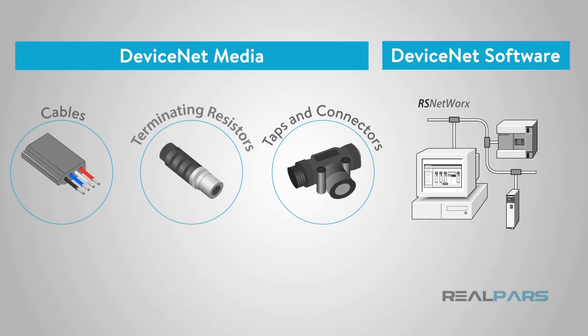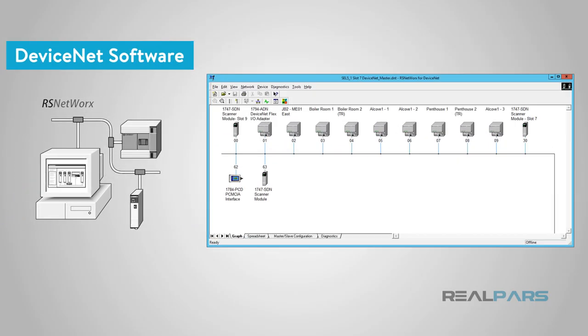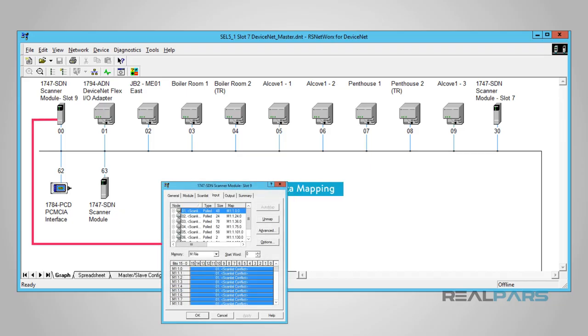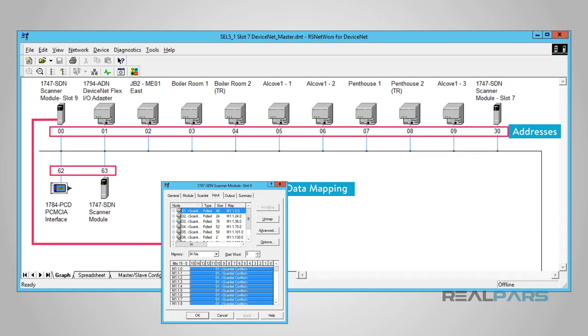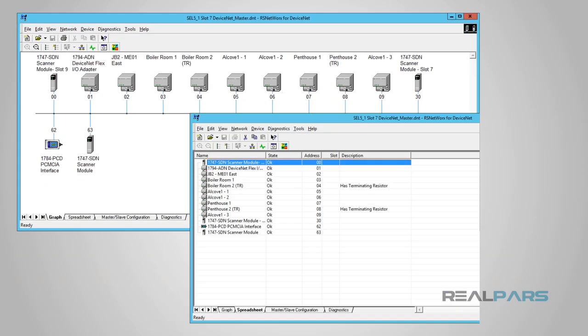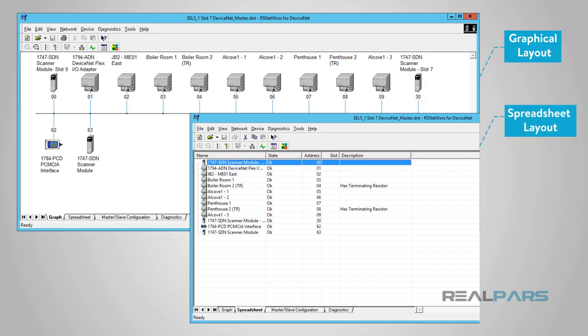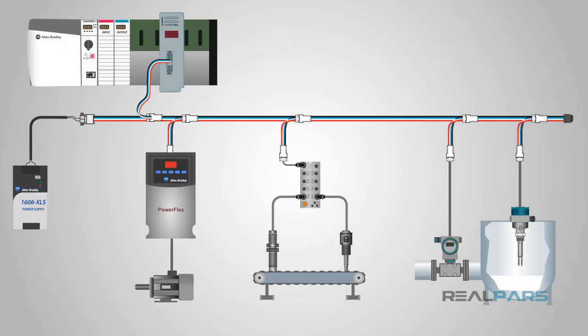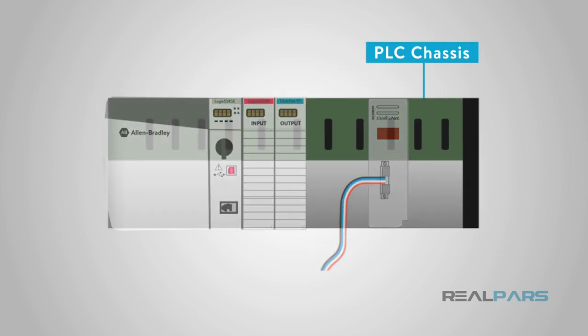Now that we have the physical network constructed, let's talk about the software side — the interface used to configure our DeviceNet network. Allen-Bradley developed RSNetWorx for DeviceNet to map and assign addresses to all the devices in the network. It uses either a graphical or spreadsheet layout to map out the network, and then the configuration is set up in all the devices and downloaded to the DeviceNet scanner. The DeviceNet scanner is a hardware piece that resides in the PLC chassis and talks to the PLC through the backplane of the chassis.